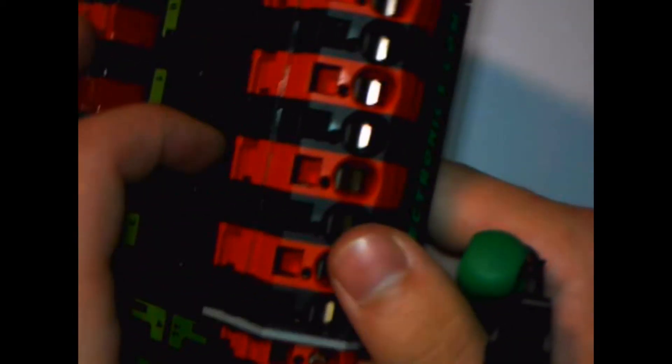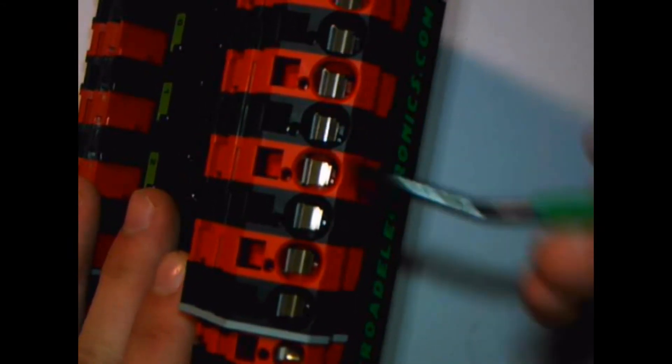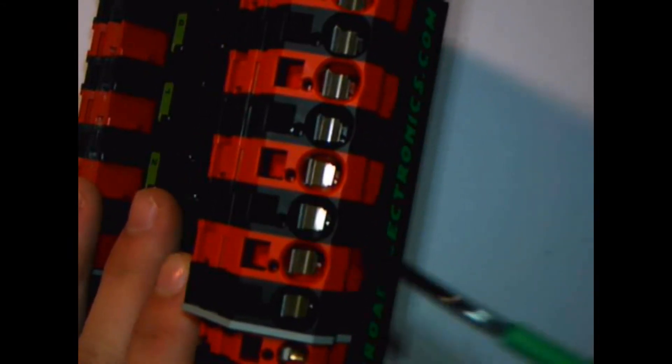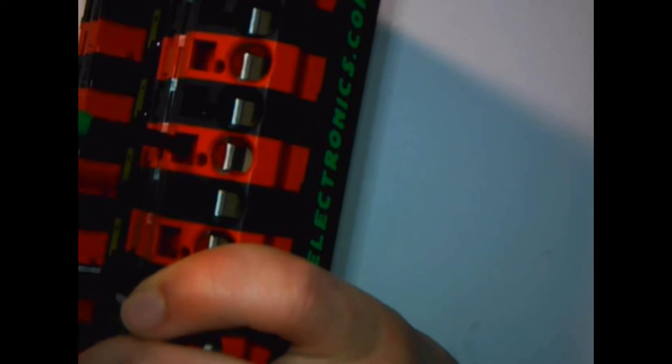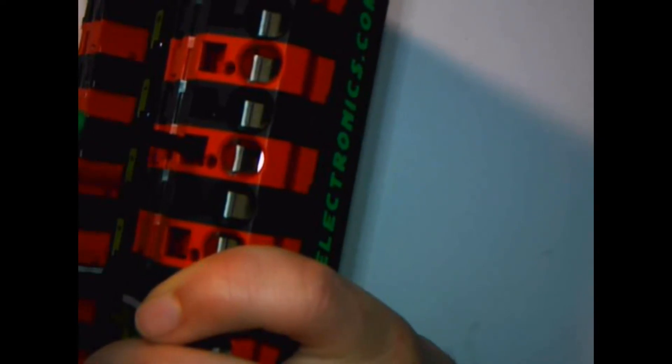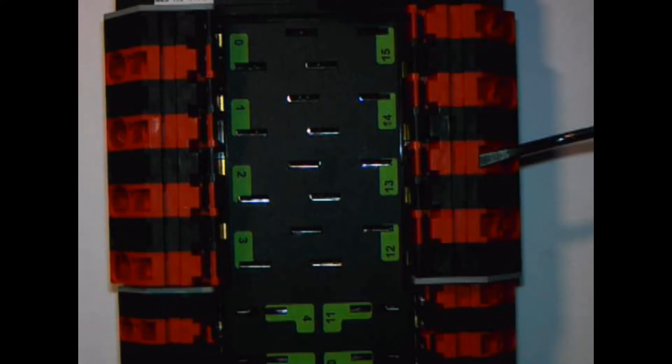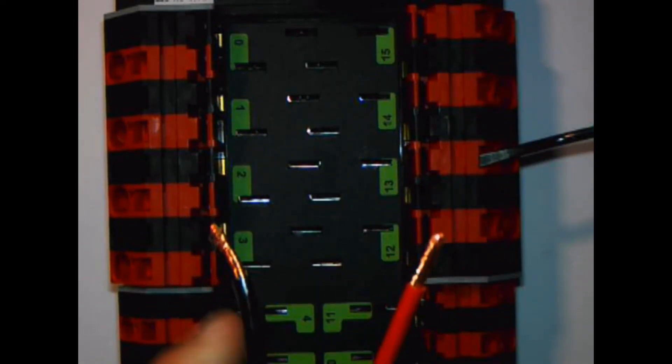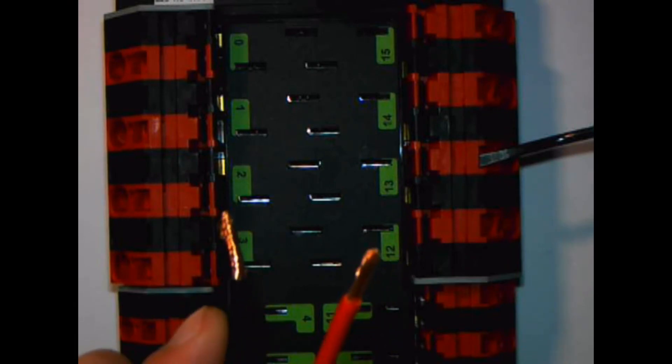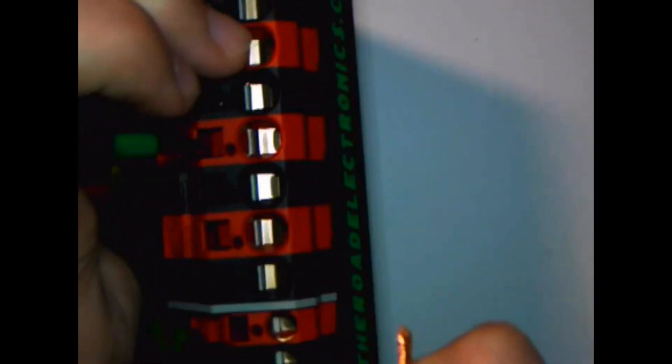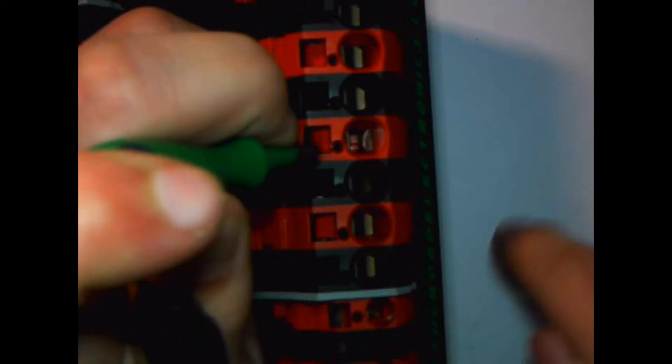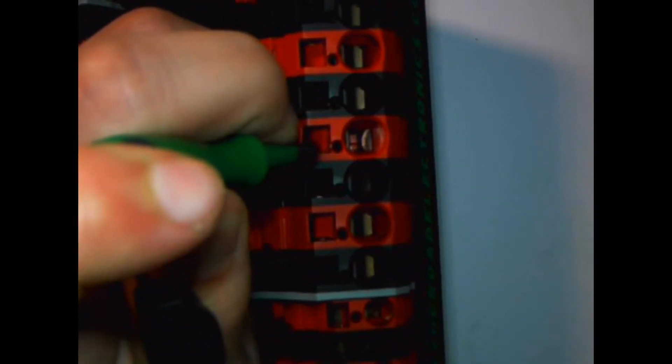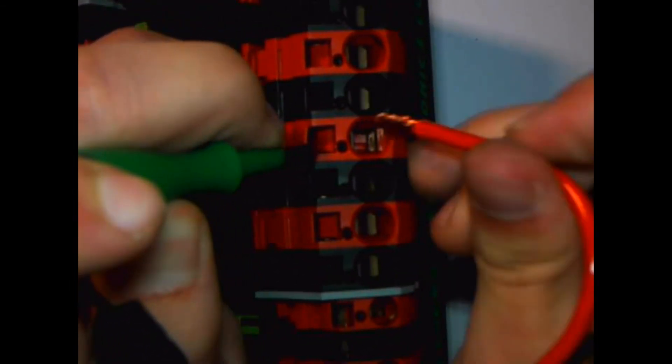So if I can show you, you'll see this tool is inserted in the top port, and the wire is inserted on the bottom port. So if I place this down in there and I open the port, you'll see that port open up, and now I have wire that I'm going to place in there. You'll see that's about the length that you want it to be stripped, maybe like half an inch or so. Then we'll open the port up and then I will place the wire in there.